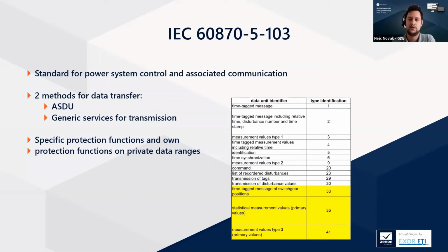A device complying with this standard can send information using two methods of data transfer: either using explicitly specified application service data units, ASDUs, or using generic services for transmission of all possible information. The standard supports specific protection functions and provides vendors a facility to incorporate their own protective functions on a private data range.